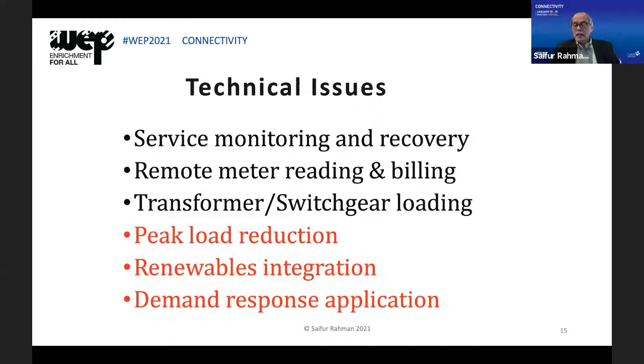Before the smart grid, when I lost power in my house, the power company didn't know how I lost power. Now they know, because even though there's no power, my meter is transmitting data over a microwave network, not the power line. Keep that in mind - microwave network, not the power line - so it's not down because that's a separate network. That gets data to the data concentrator, which uses the phone network GPRS to send data to the substation. That's how they know my house has no power, and they can work on that. Number 1.